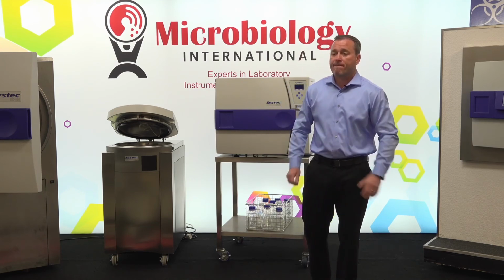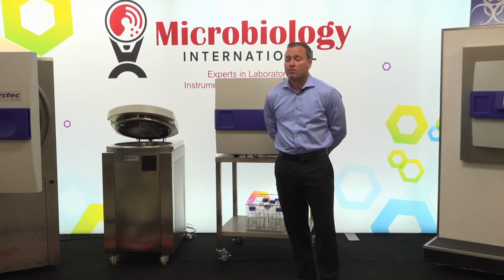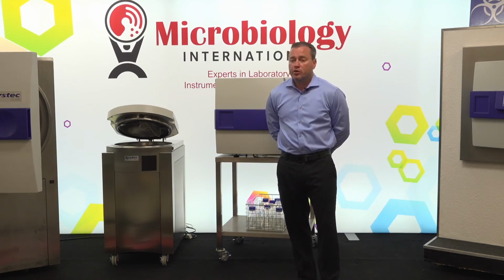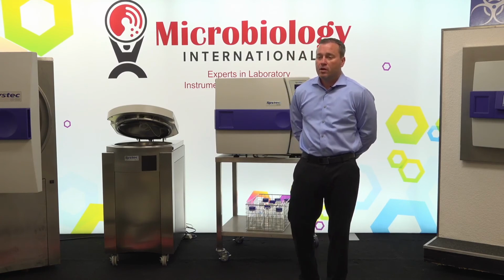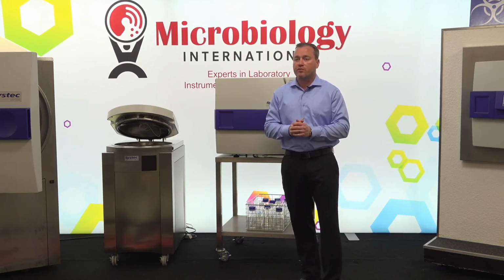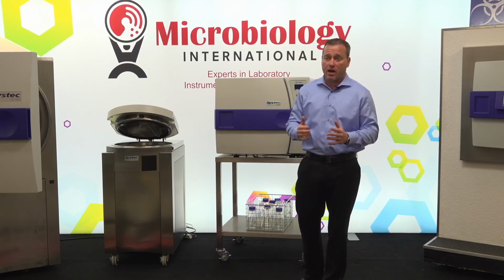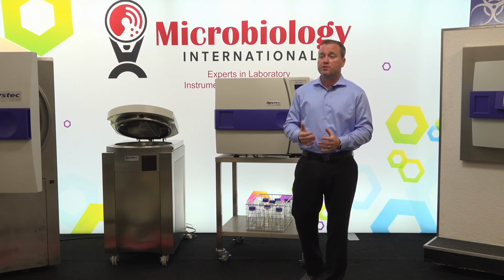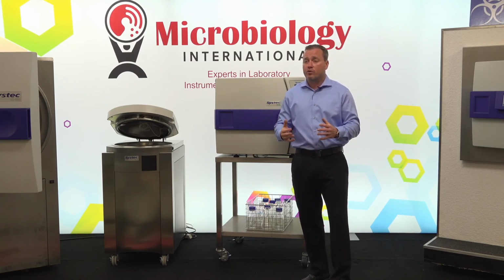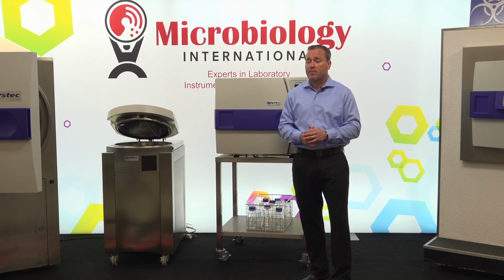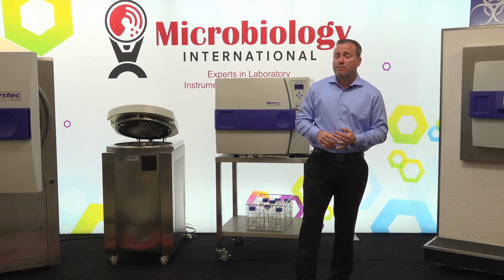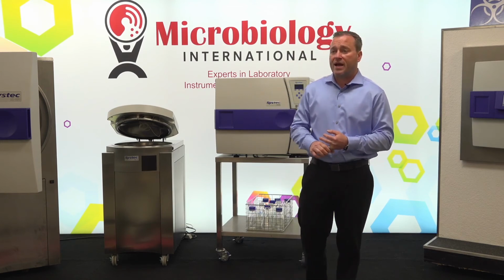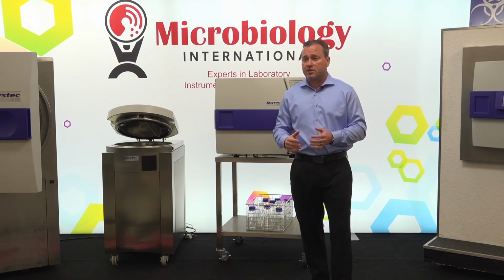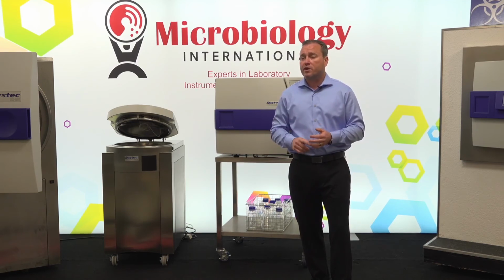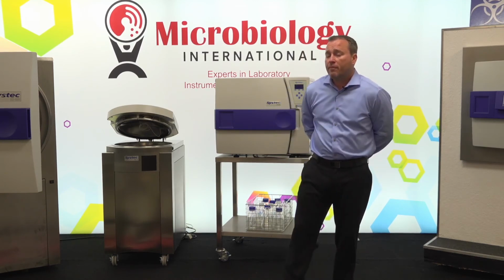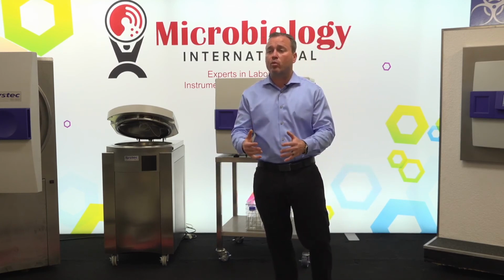All right. Next would be service. Is that recommended yearly or as needed? We do recommend having at least a PM every year. Now, I know customers have purchased our units from us and have used them for 5 or 6 years and never had us come see them, which is good because the instrument is still working. However, we do recommend if you're going to invest in a system to make sure that you get at least a yearly PM. We can do not only the preventive maintenance on site, but again, calibrate all of the temperature probes to NIST traceable standards. When you receive the instrument, it will have a full 1-year warranty with all pressure transducers and probes, temperature probes, calibrated to NIST traceable standards, which again, we can redo that for you on site.